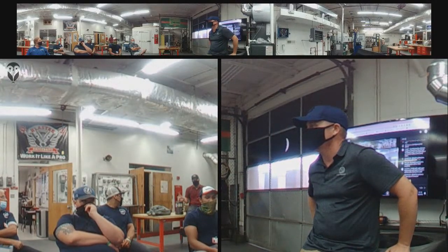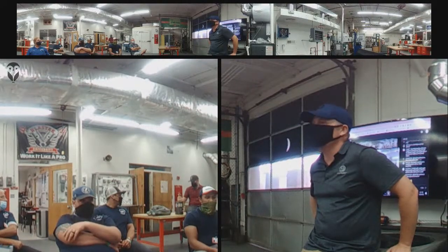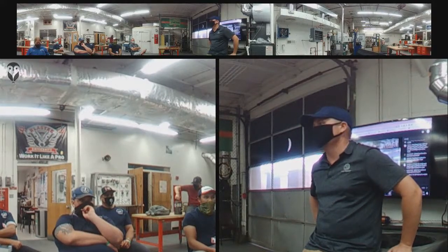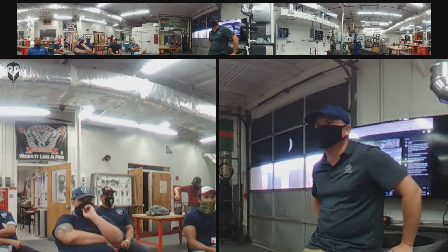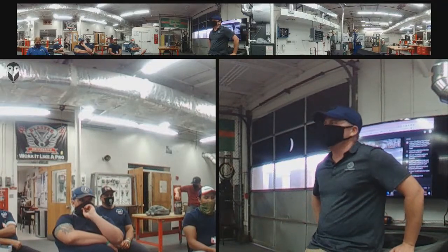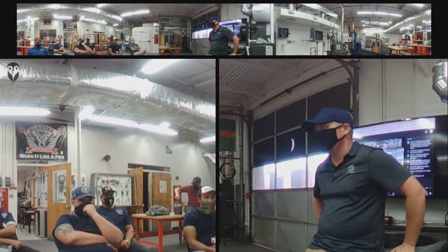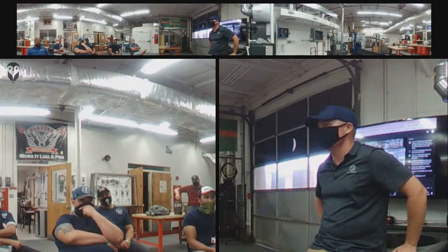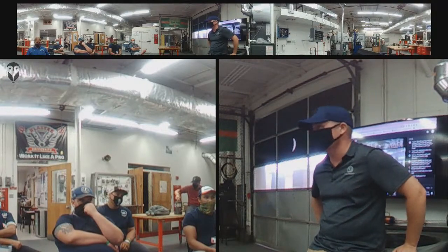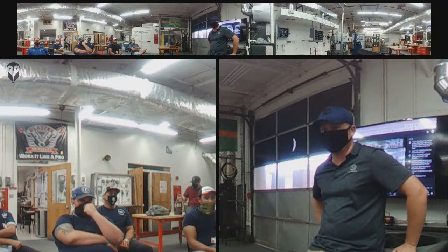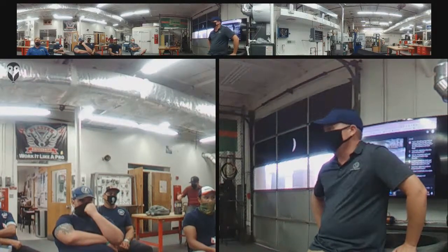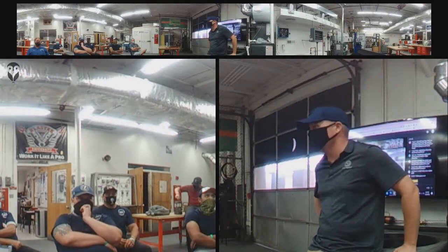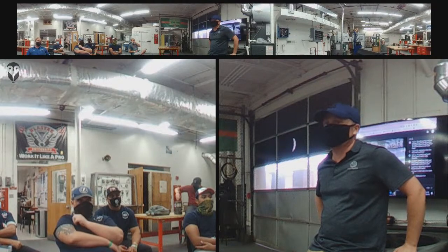Because the Y call on certain boards will turn on the blower motor, but it will turn it on into super dehumidify mode. That's a Carrier term. I don't know that all brands do this, but if you have a Y call without a G call, sometimes on some equipment your blower will run, but it will just run slow. So that's something to always check for. If you've got a blower that seems like it's running too slow, check if it's wired up for dehumidification, make sure it's not in dehumidify mode, and then also make sure that you've got a call on G.